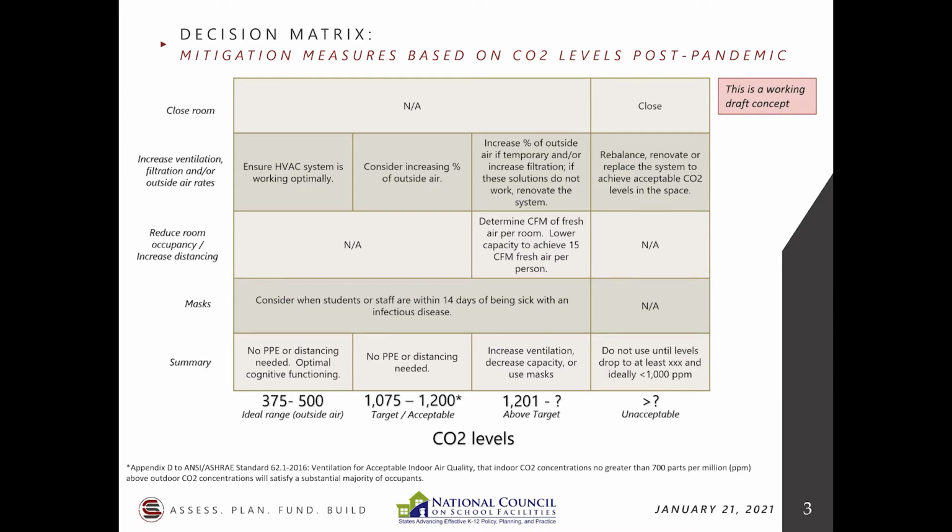I love to hear these, and I'm sure you all do too, whatever you want to call them, platitudes. Yeah, bring in 100% outdoor air. Is that real world? Can you do that with our system? No, you can't. Think of a hot, humid climate. You're going to be replacing one problem with another if you cannot handle the latent load. So I don't know if there is an exact value that you could say at this point what we should be trying to meet. Definitely, we should be meeting minimum standards, but we try to exceed that. Do the best you can.